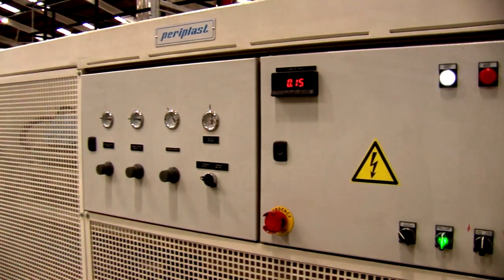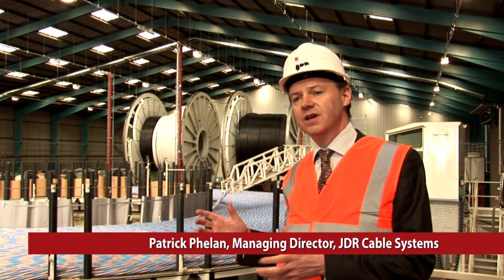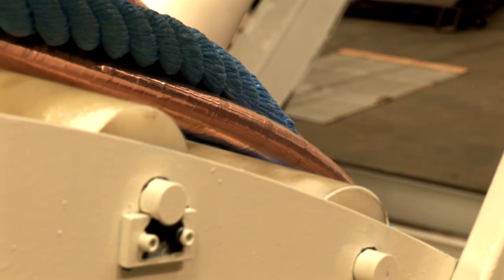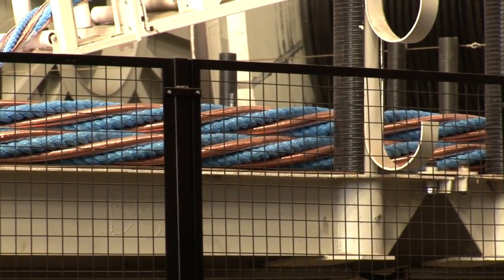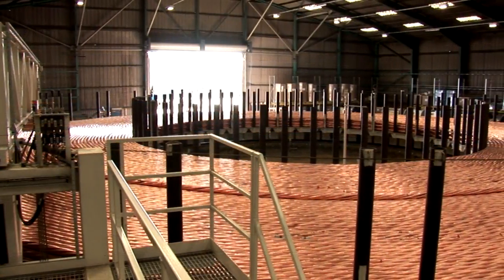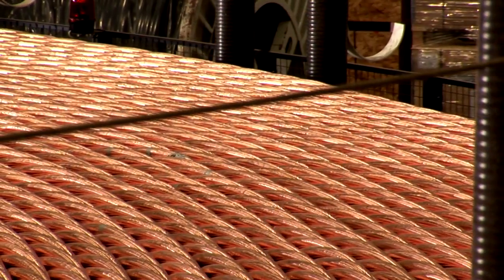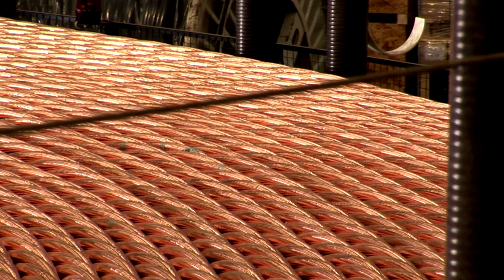We're building a 25km power cable, which means twisting together six 33kV capacity power cores along with two fibre optic cables. We will then sheathe this 25km length with polyethylene and put two layers of high tensile steel armour over the top, followed by a final sheathe. That will then be connected with the Wave Hub itself, and four connecting cables will come from the Wave Hub.